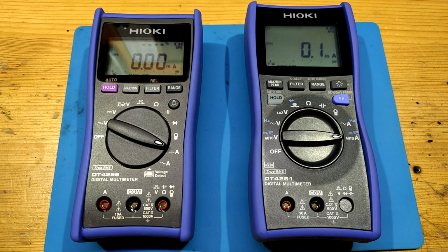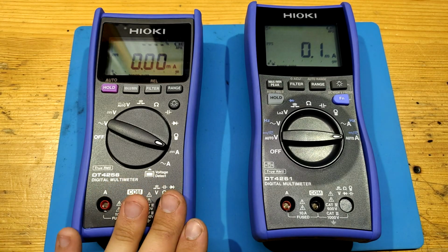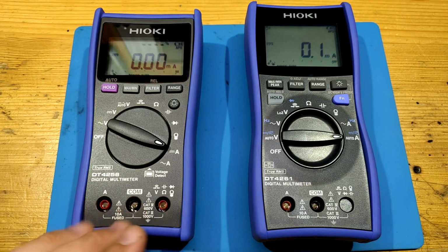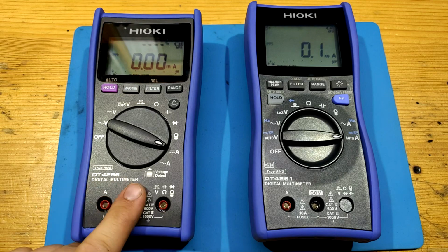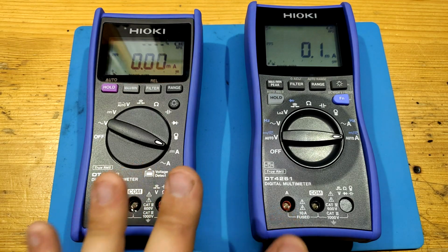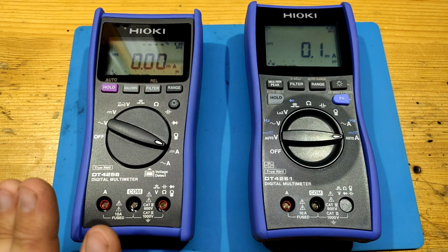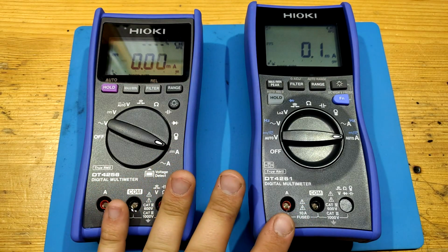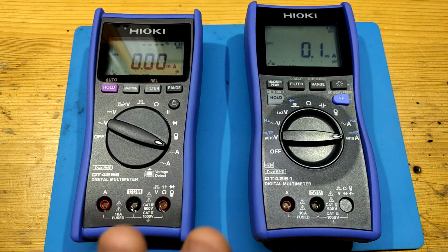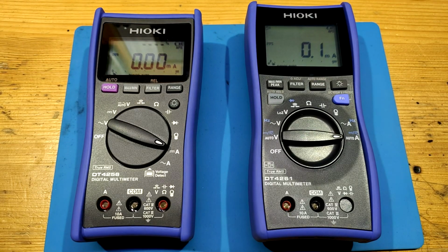Well, so I was applying 9 amps for 1 minute and the error climbed to 0.08% from range. Beautiful, really beautiful. 0.08% is definitely a measurement, and good one. If you overload the current range above 10 amps, meter makes sure you know you screwed, so you have the opportunity to save your HRC fuse from blowing, and these aren't cheap and you can't find them everywhere.